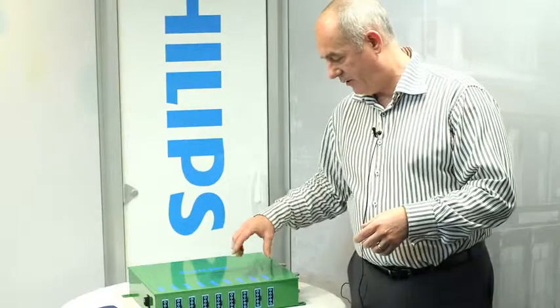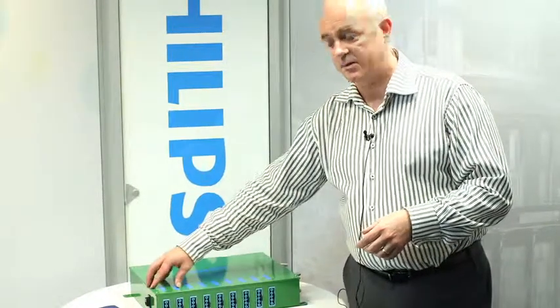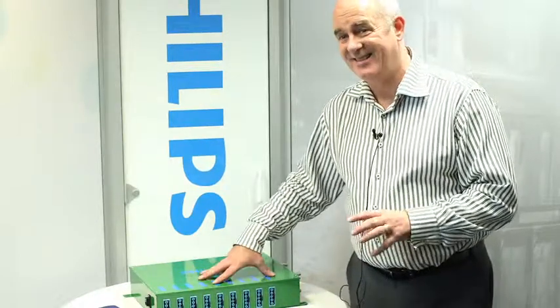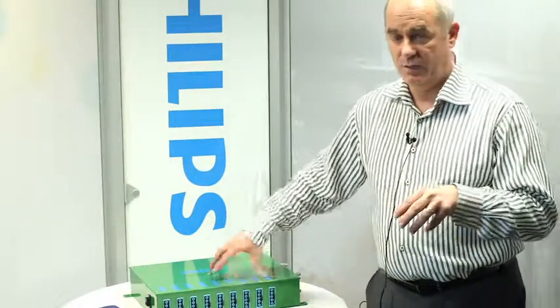In here, we have three separate DALI universes, each capable of providing power and DALI control to up to 50 luminaires per universe out of three sockets.